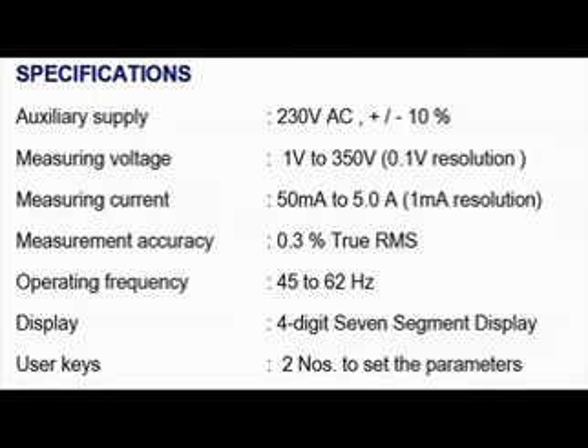We have a version of this board which will also work for current. So in the case of the current, we can measure from 50 milliamperes to 5 amperes with a resolution of 1 milliampere. The measurement accuracy is 0.3% true RMS, but in lab tests we have seen that the accuracy can be at 0.1% and even better.